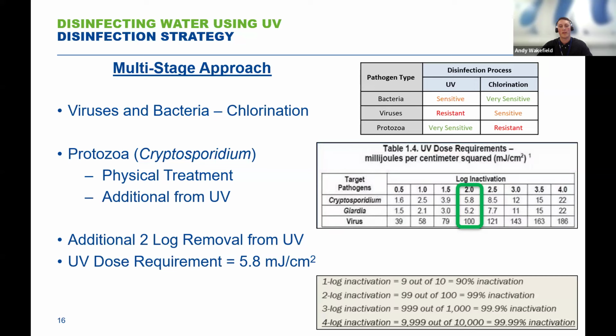Crypto is very sensitive to UV light, and you need relatively low UV dosage to effectively kill or render inactive the cryptosporidium cells. So we needed to quantify what level of UV was required to future-proof the works, and we settled on a 2-log removal. So this is essentially a 99% inactivation. And to achieve that, you only require a 5.8 millijoules per centimeter squared UV dose, which is relatively low when you compare that to what would be required for virus inactivation at 2-log removal. You would require 100 millijoules per centimeter squared for the same sort of inactivation of viruses. So it shows the difference there in how effective the UV dose is.